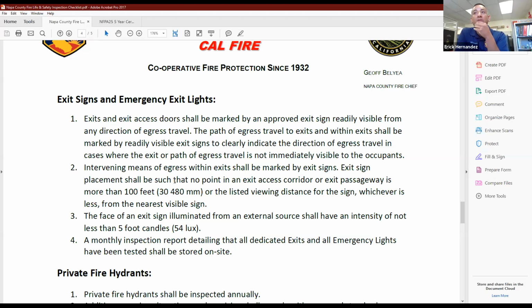Typically when PG&E shuts the power down to certain areas, unless you have a generator, that's where your battery backup will come into play. Sometimes we're finding that the batteries in these exit signs are being drained, because they're meant for 24 hours of battery backup, and sometimes these power shutoff events go beyond 24 hours. So that's the purpose of doing a monthly internal inspection and keeping a proper log.